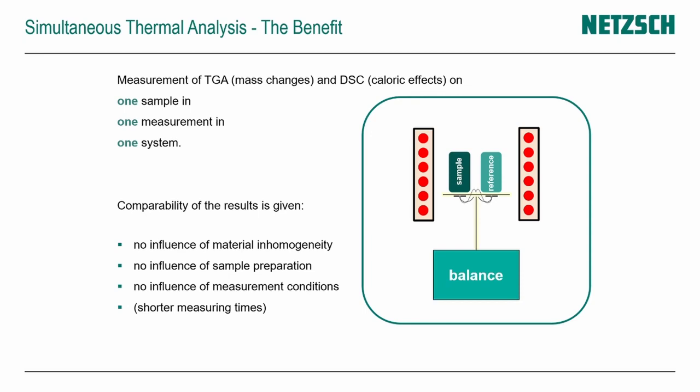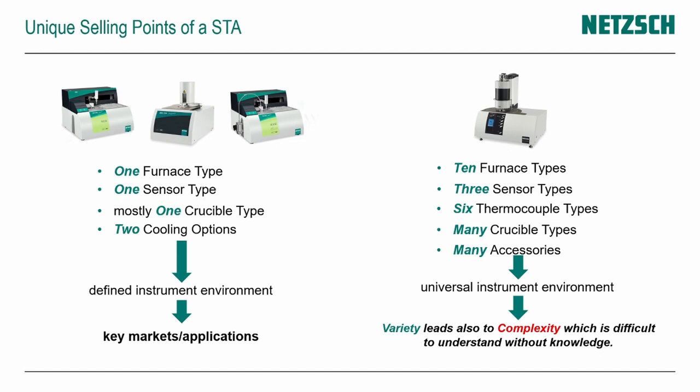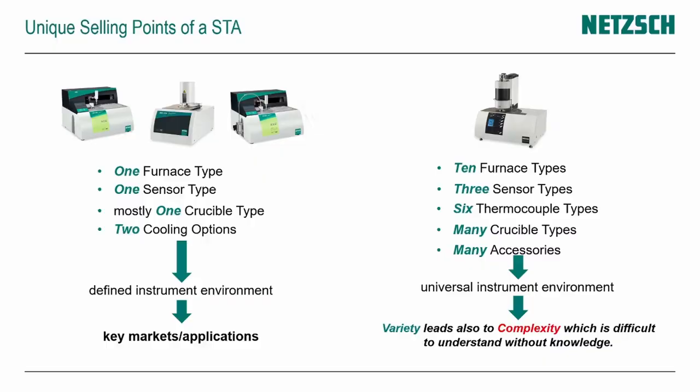Let's dive deeper into the comparison of dedicated methods versus combined methods. In our portfolio, the dedicated systems are quite defined — one furnace option, one sensor option, typically one type of crucible: alumina crucibles for TGA or aluminum crucibles for DSC analyzers. There is some range of choice for cooling options. Nevertheless, the dedicated systems provide a defined instrument environment and are designed for special key markets, especially the low temperature range for polymer or pharmaceutical analysis fields.